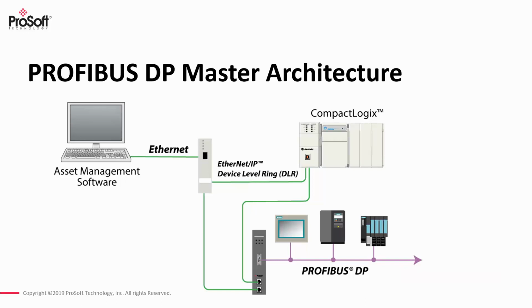One of the things we are excited to announce, or premiere, on this new product is that this is our first module that supports DLR, Device Level Ring. That gives you a redundant Ethernet network and allows you to participate on those DLR networks that have been widely adopted within the Rockwell Automation platform. CompactLogix and ControlLogix all have options for DLR networks. DLR is a self-healing, redundant Ethernet network.